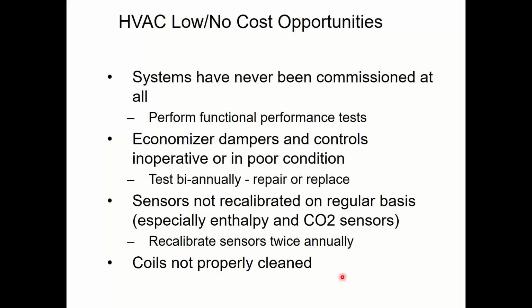And then I need a food source, something organic for the mold to eat. Well, an aluminum or copper material in my coil is not a food source. Mold will not eat metal. But if I have debris on there that came through the air, like pollen or whatever it was, that is organic. Now the mold can sit on there and eat that. So if I do a good job filtering, I don't have to clean my coil as much. And I don't want to say never, but possibly never. Not never, but not very frequently. But if you have crappy filters and all that crap's coming through, then you're probably going to have to clean it more often. So possibly you're having to clean, say, your evaporator coil, I don't know, once every 2 years, unless you do a good job filtering, or you put a UV light like we talked about last week on there to keep the coil clean.